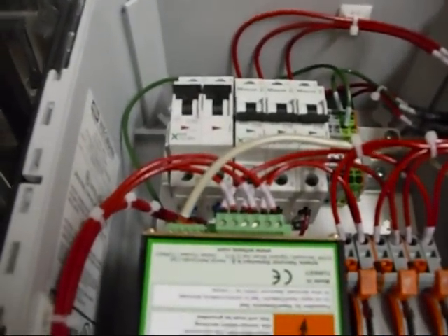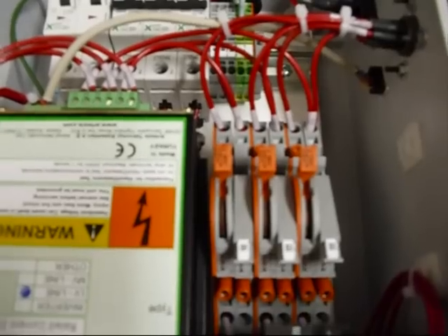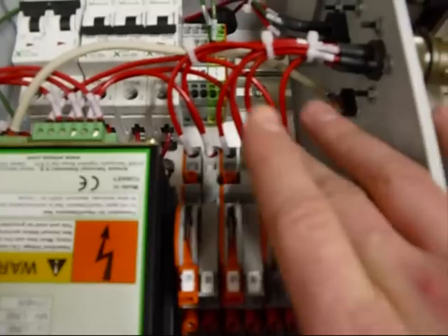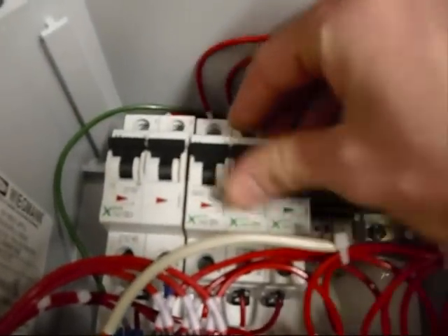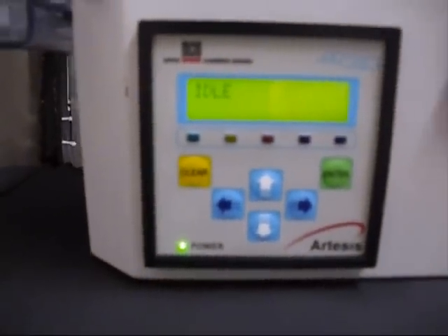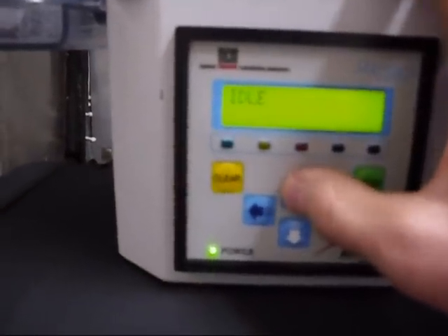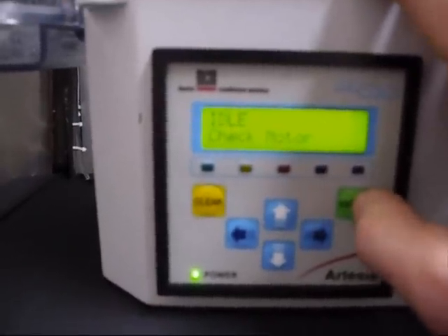The final step in the process, we're going to connect everything. So you see we still have the CTs with the shorting links connected. We're going to connect these. I haven't killed myself, so I'm assuming this is okay. We're going to connect the voltages. So we should have all the connections coming into this thing that we want. The next stage, we press up once. You can see it says check motor. Enter, enter.